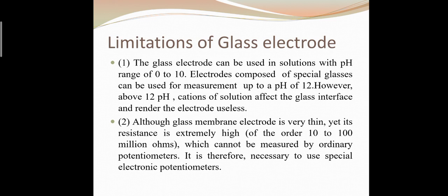So we cannot use it for a solution whose pH is over 12. It is useful for 0 to 10. However, in some special conditions, by using special glasses, we can measure up to pH 12, but not more than that, as destruction of the glass electrode may take place.